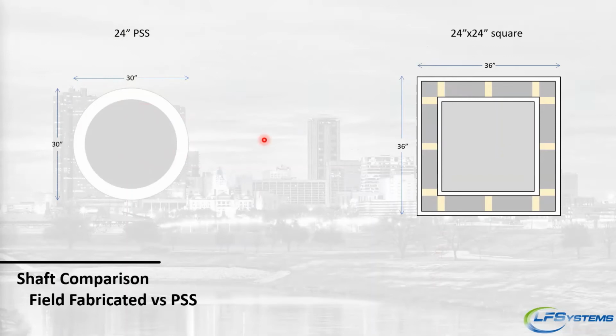Now, the first thing people say is, well, 24-inch round is not the same as 24 by 24. That is true. However, what we've found is that in the actual flow characteristics of a vertical shaft, the corners play very little role in the amount of flow that's available in that shaft. So typically, we will just round those off anyway. So a 24 round can, in most cases, handle the same capacity as a 24-inch square. So we're going to save you about 6 inches per shaft, both left to right as well as top to bottom.